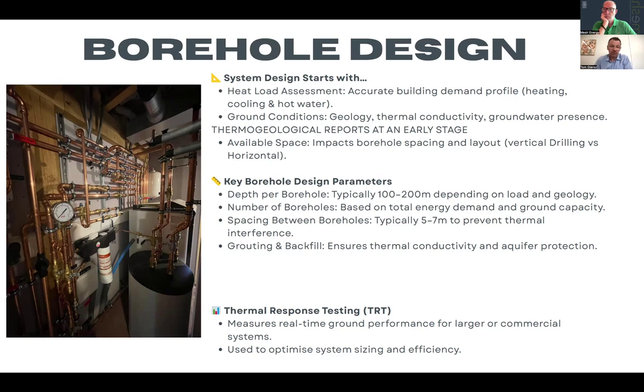square meterage of the property. That depends on the insulation. So you can be looking at 10, 15, 20 meters, 20 boreholes. So we are talking about a 60 to 100 kilowatt system. And the commercial system we were talking about was, I think, about a 1.5 megawatt system.